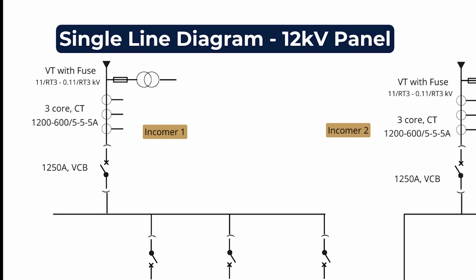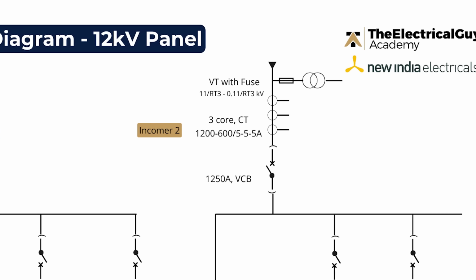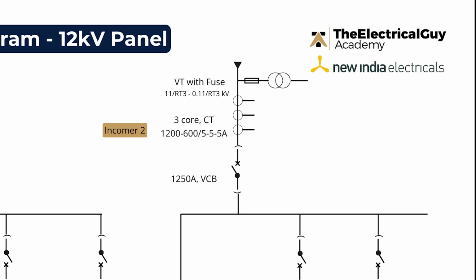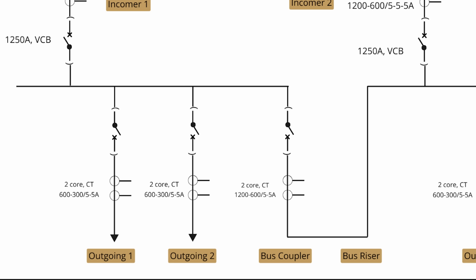So that is basically our incomer panel 1. And if you look at incomer panel 2, which is very much identical to incomer panel 1, we have VT with fuse, 3 core current transformer and again a withdrawable type vacuum circuit breaker. So those are the 2 incomers that we have. Now moving on to the outgoing one, you see we have another vacuum circuit breaker. Of course we need protection for the outgoing as well. And this is also withdrawable type. The rating of the breakers is the same. And here we are using a 2 core current transformer which is rated at 600 by 300 and the secondary current is 5 ampere.